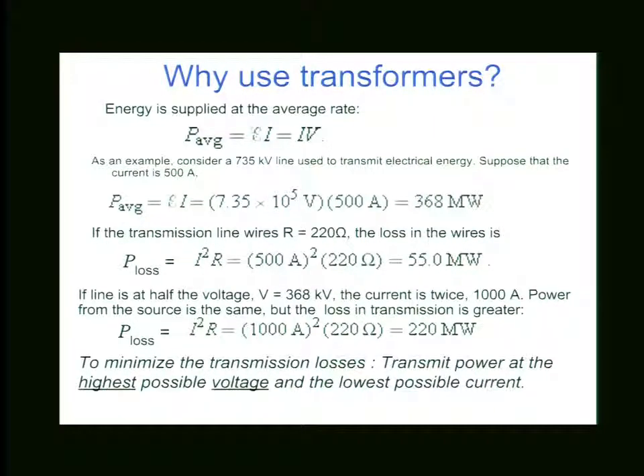But on the other hand, if you were to transmit that power at a lower voltage with higher current, say double the current, like 1,000 amps, running through that 220 ohms, you would waste 220 megawatts. You'd probably use up all your energy just transmitting the power.